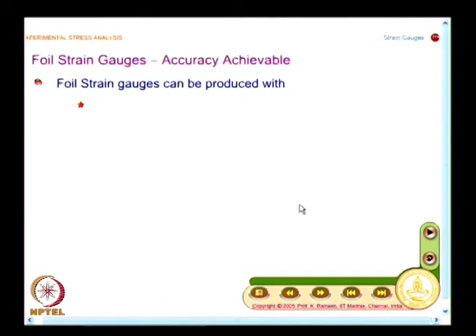And using the principles of solid mechanics, I can have a bridge factor up to 4. This may be good enough in the case of transducer applications. In normal strain measurement, you may paste just one strain gauge. And what is the level of accuracy that we can think of? This depends on what way we get individual accuracies of the various factors influencing the strain gauge instrumentation. And what is the accuracy achievable? Foil strain gauges can be produced with gauge resistance accurate to plus or minus 0.3%.